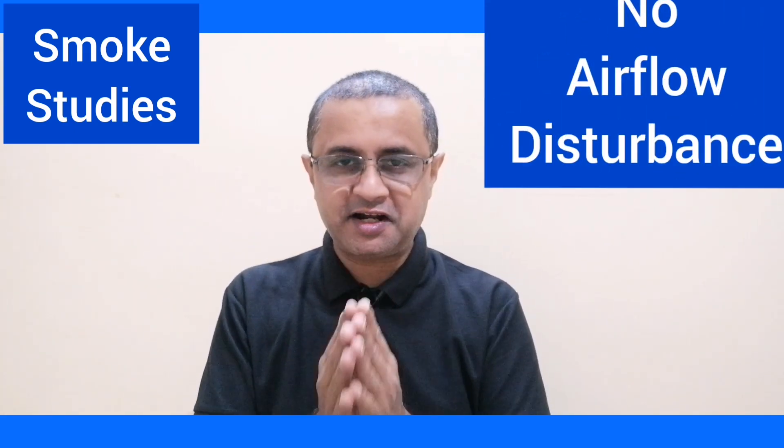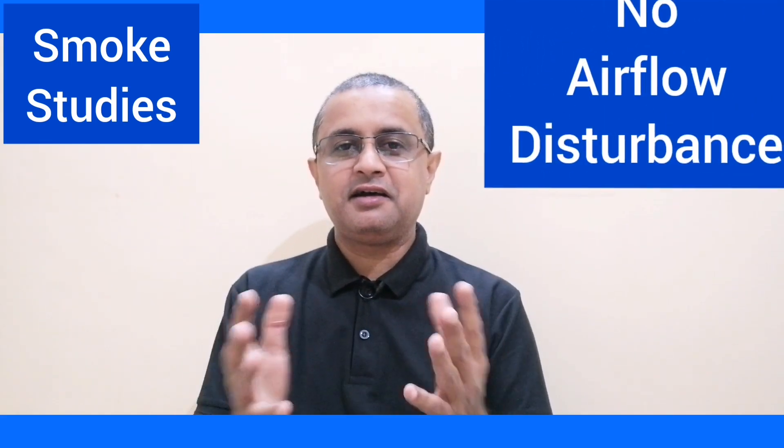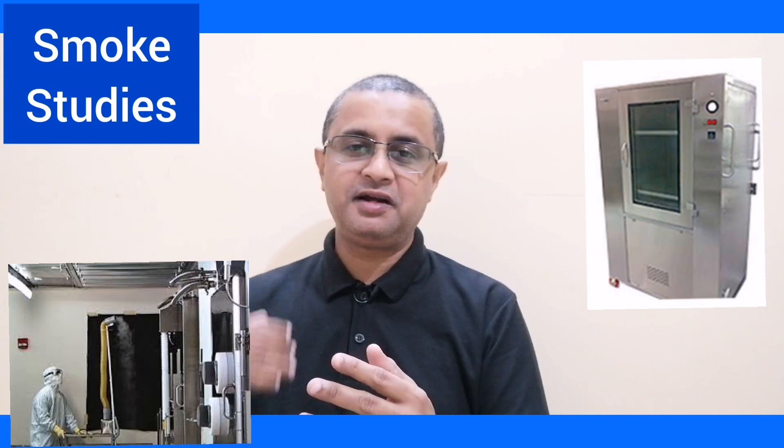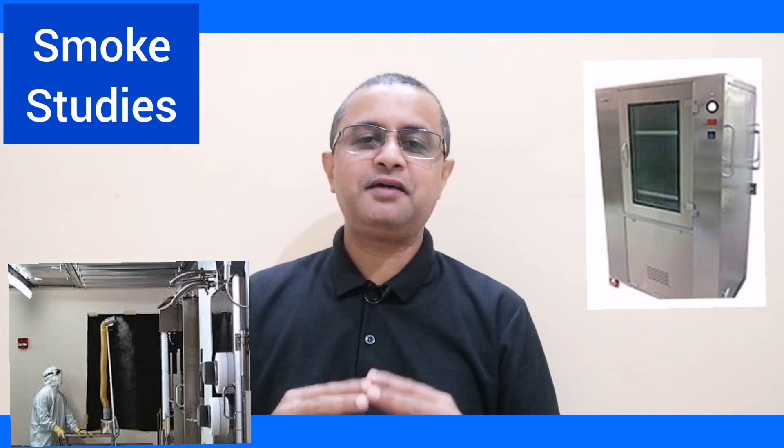Whenever we are transferring material from Grade B to Grade A — before our filling assembly — we have to demonstrate through smoke study that while transferring the material we open the filling machine doors, and even if it is an isolator we have to open the door to transfer the material inside. It must be ensured that the airflow from the filling machine is going outside to the Grade B or Grade C surrounding area, and not from the outside area to inside.